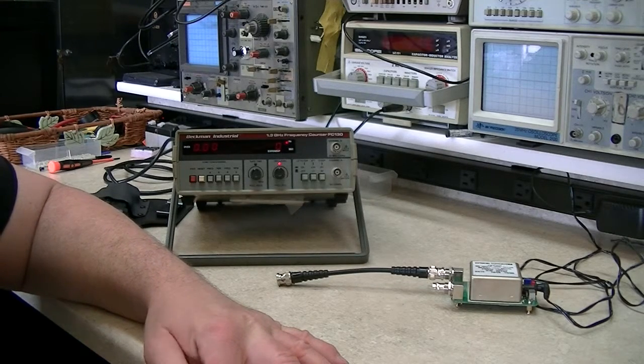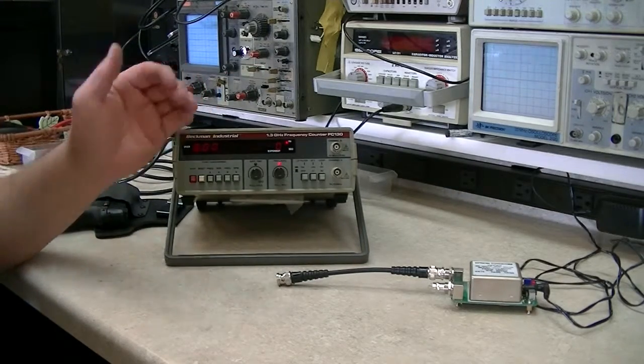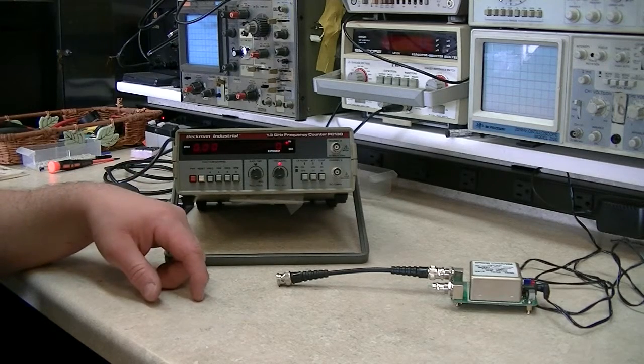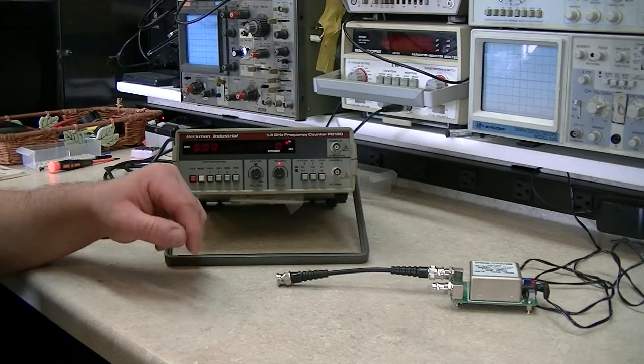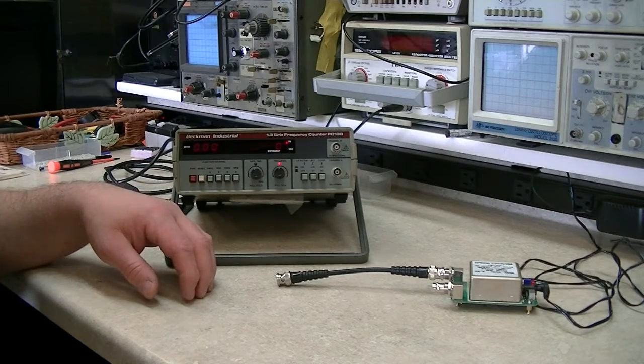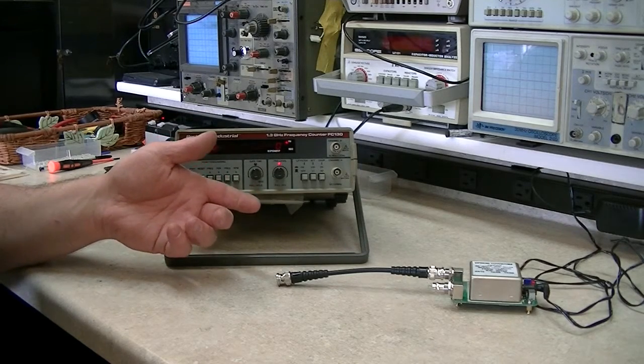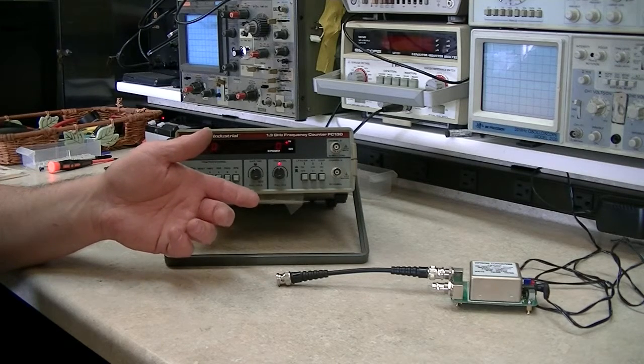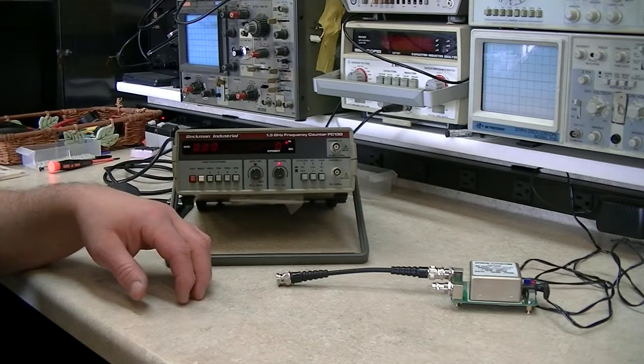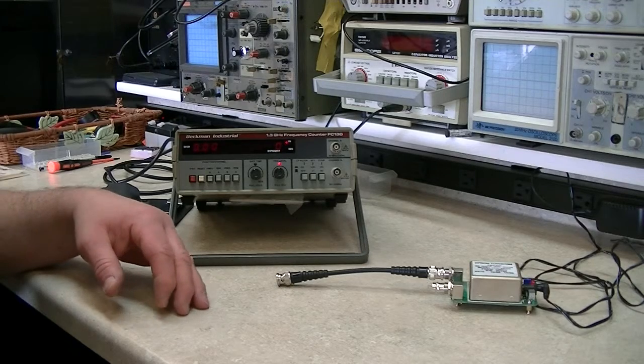Now one problem with these is they're not really a laboratory instrument, they're more of a service instrument, and they don't have an oven-controlled reference oscillator. Generally, all they have is a 10 megahertz crystal with an oscillator circuit around it. I haven't studied it close enough to tell which type of crystal oscillator circuit it is, but it's definitely sensitive to temperature.